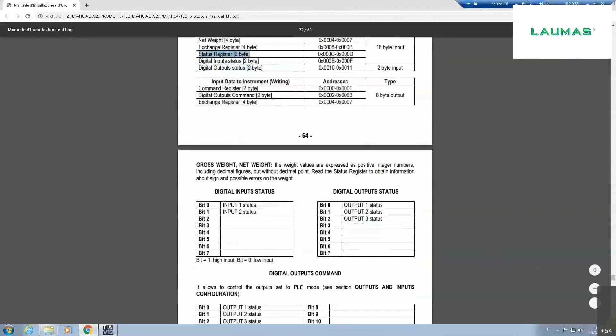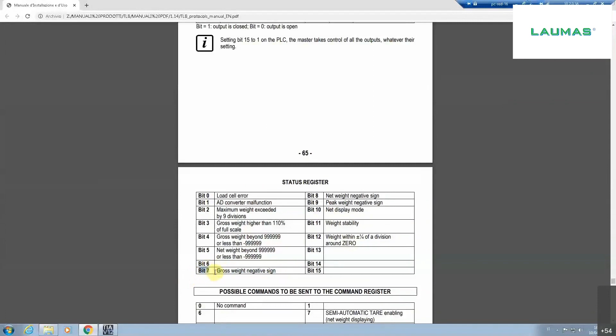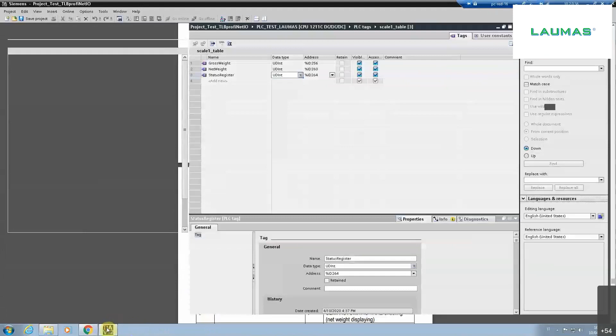And exploring this table, we see that, for example, the bit 7 value gives an indication about the sign of the gross weight value. More specifically, if during the communication we find a value for the status register corresponding to bit 7 equal 1, this means that the received gross weight is a negative weight value.